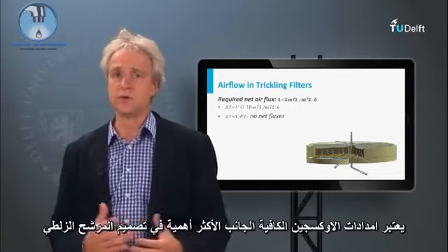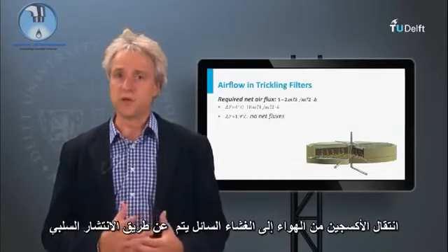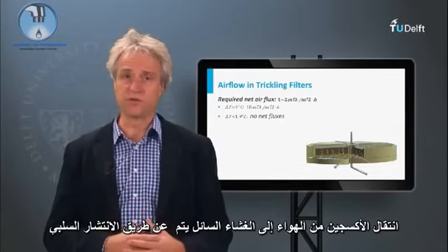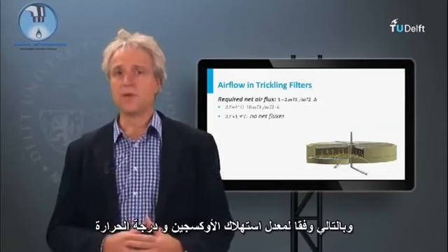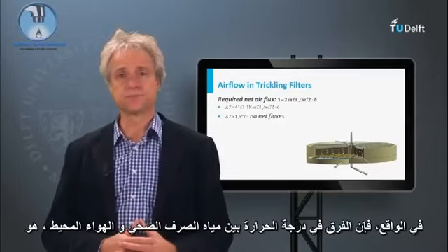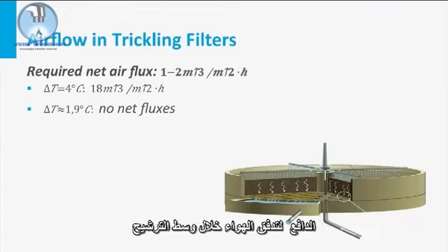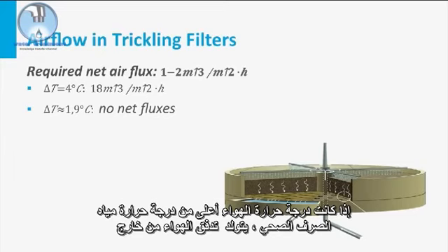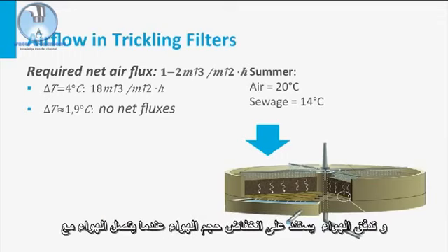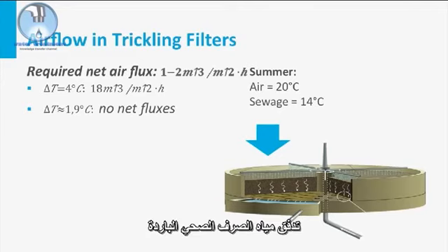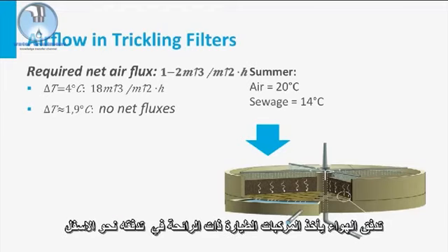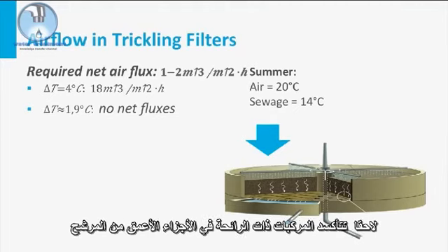Adequate oxygen supply is considered the most important aspect of a trickling filter design for sewage treatment. The transport of oxygen from the air to the liquid film is driven by passive diffusion, thus by the oxygen consumption rate and the temperature. In fact, the temperature difference between the sewage and the surrounding air is the driver for convective airflow through the filter bed. If the air temperature is higher than the sewage temperature, then an airflow from outside the filter to inside the filter bed is created. This airflow is based on the decreasing air volume when the air comes into contact with the cold sewage flow. The airflow takes possible odorous volatile compounds in its downward flow, and these odorous compounds are subsequently oxidized in the deeper parts of the bed.